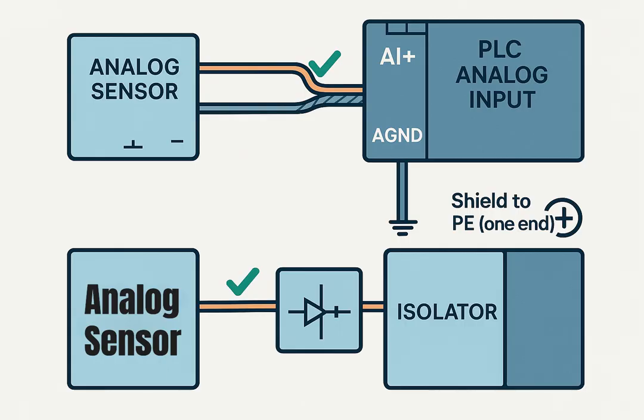So what is the correct way? On most PLCs, you will see AI plus / AI minus, or AI / AGND, or I plus / I minus for 4 to 20 milliamp signals. The rules: Sensor positive, VOUT plus or IOUT plus, connect to AI plus or I plus of the PLC. Sensor ground, VOUT minus or return, connect to PLC analog GND / AGND / AI minus. This is the reference point used by the PLC's analog circuitry.